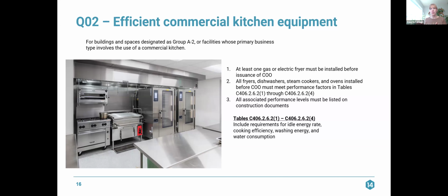So here are the requirements 1 through 3. At least 1 gas or electric fryer must be installed before issuance of the certificate of occupancy. If you do not have a fryer, you cannot comply with this section. Number 2, all fryers, dishwashers, steam cookers, and ovens installed before COO must meet the performance factors in tables C406.2.6.2(1) through C406.2.6.2(4). Those tables, and I have this kind of below right there, include requirements for idle energy rate, cooking efficiency, washing efficiency, and water consumption.